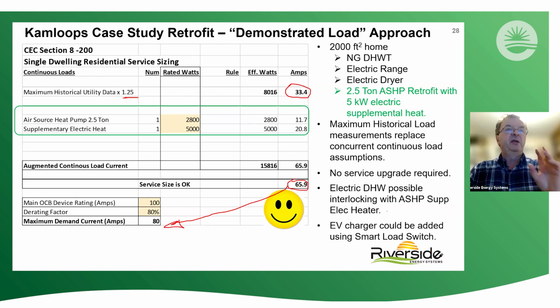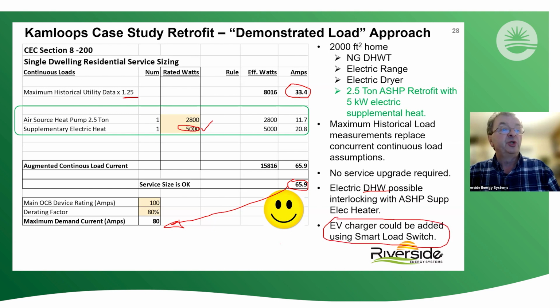And in fact, I could even add an electric hot water tank and an EV charger. If I interlocked the domestic hot water tank with the supplementary electric heater, we'd be fine. I'd only have to count the electric boost heat, which is the bigger of the two. And I could add an EV charger if I used a smart load switch and didn't even need to count it here. So this is a real example where a retrofit could be done using demonstrated load and interlocking and a smart load switch to control the EV charger and not require a service upgrade from the 100 amp service.